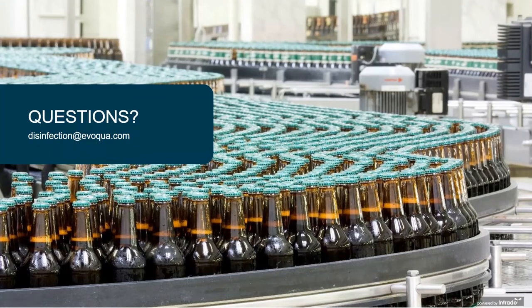Great. And then we have a question asking, what is the optimal temperature for ozonated water surface disinfection, i.e. bottles and caps? So ozone does have a half-life for effectiveness, and its half-life is predicated on water temperature. So actually the colder the water, the longer ozone is going to be at a specific concentration. So anywhere up to, you could safely use ozone in controlled concentration for those applications up to 80 degrees F and feel pretty confident that you should not have any concerns using that as a primary disinfectant for those components.